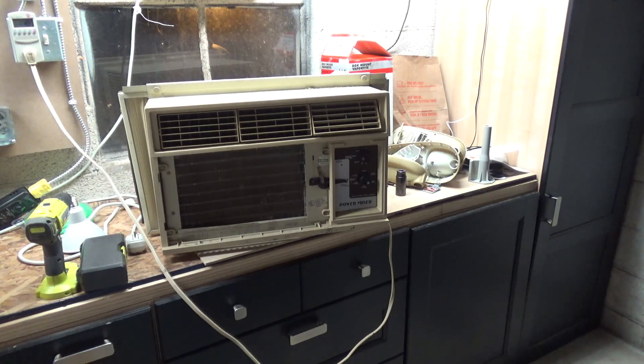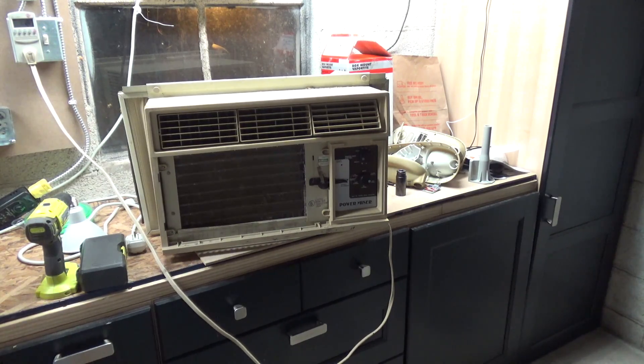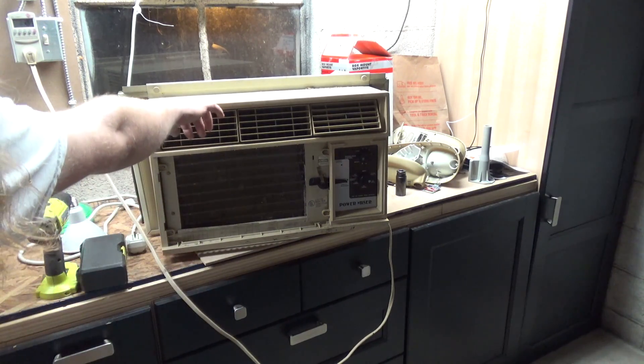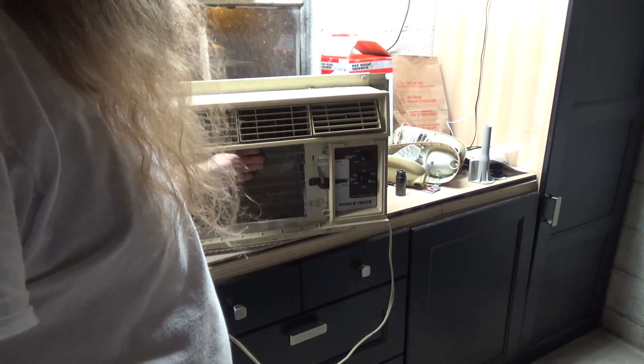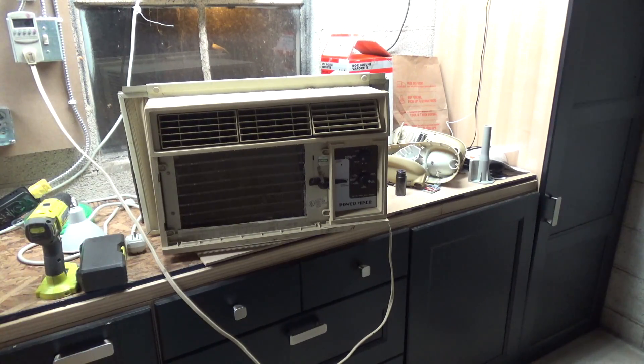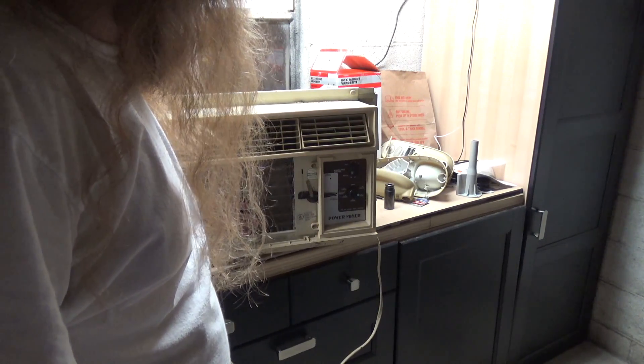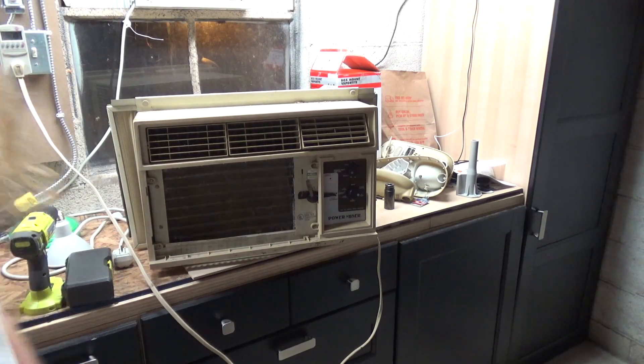Very chattery compressor. It's cooler than the ambient but it's definitely not cold yet. The coil doesn't feel that cold at all. We'll give it a few minutes to do its thing and come back. It's been a few minutes — we're up to 4.1 amps so the head pressure is still building. It's going out kind of cold now, but I can only feel like the bottom two rungs are really cold, so it's taking some time.